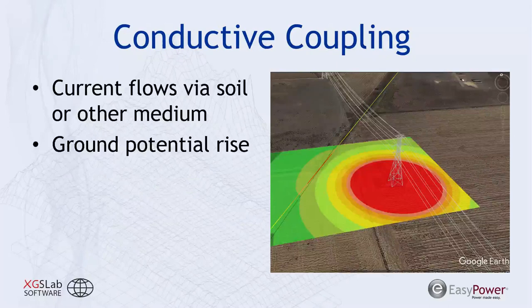And our third type, going in a little more detail, we have our conductive coupling. Here on the right, you can see an export from XGSLab. We have a transmission line that's experiencing a fault, and there's a ground potential rise from that fault current, and that ground potential rise is conductively coupling or transferring its voltage and current to an adjacent pipeline, elevating that pipeline's voltage and transferring that out.